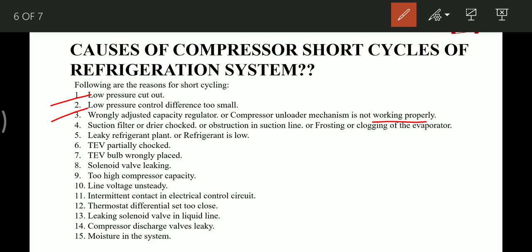Then we have suction filter or dryer choked, or obstruction in the suction line, or frosting or clogging in the evaporator. These are the reasons that can lead to short cycling. Then we have leaky refrigerant plant or refrigerant in the system is low. Then the thermal expansion valve is partially choked or its bulb is wrongly placed.